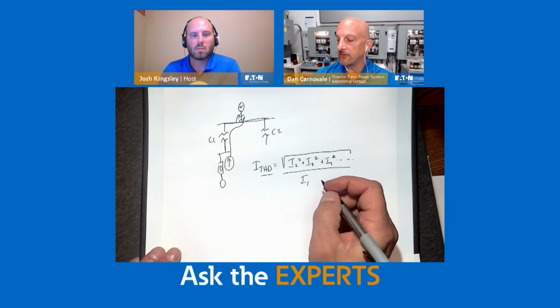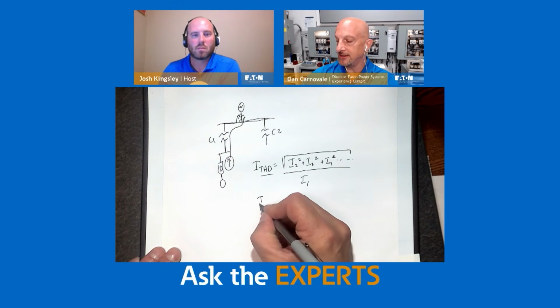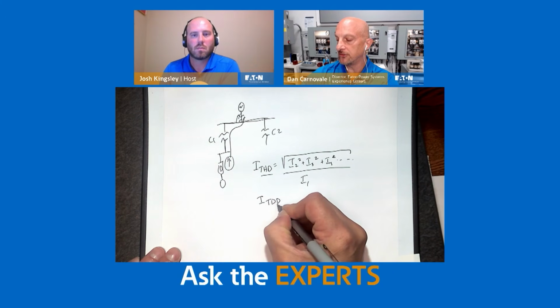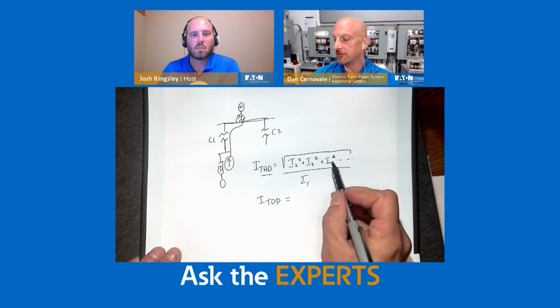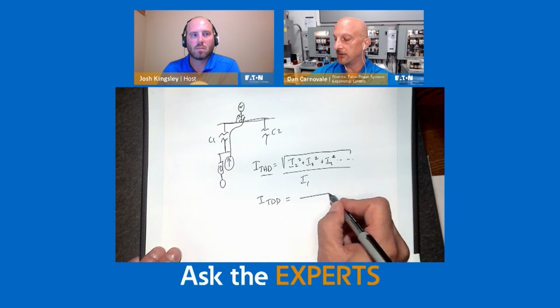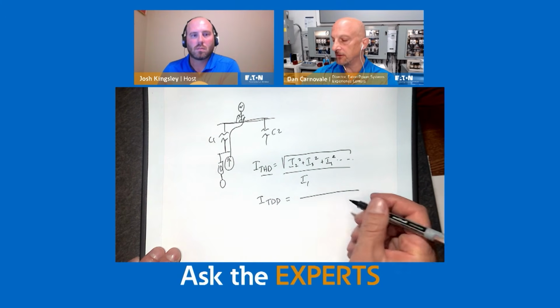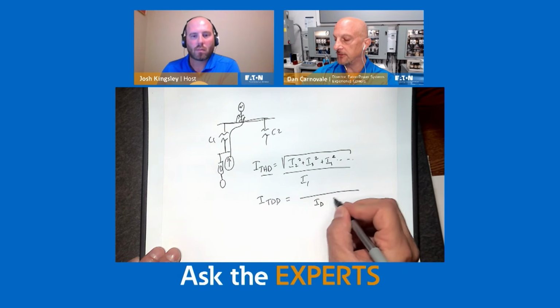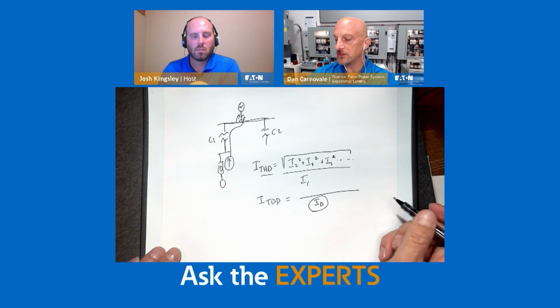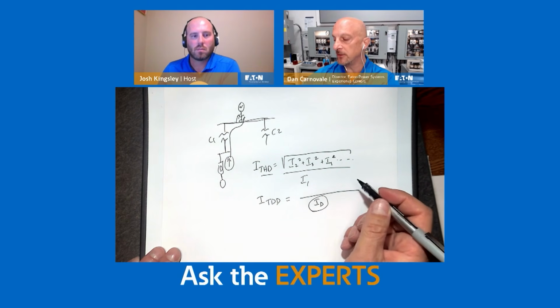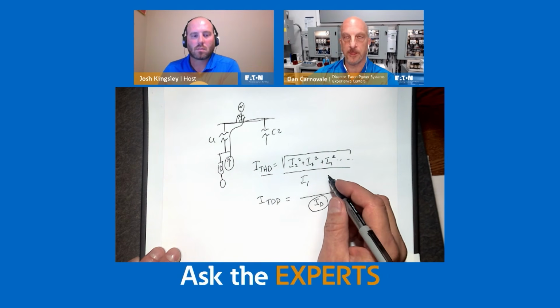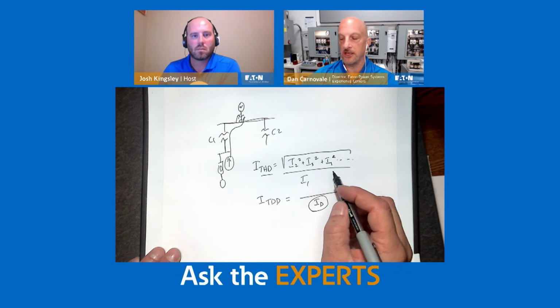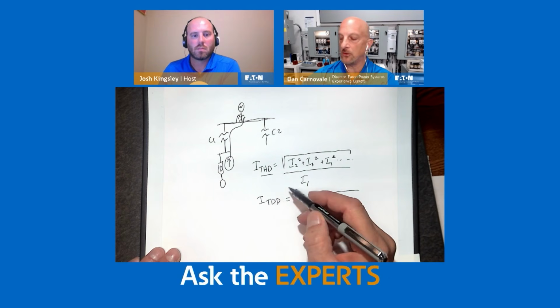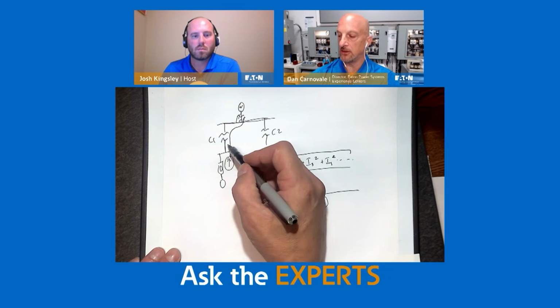With the IEEE 519 standard, they changed that to ITDD, total demand distortion. And what that means is everything on the top is relatively the same, except you're using kind of a worst case scenario demand. And then this is the demand situation when you're at your peak. So you might have really light distortion, or let's say in terms of amps overnight, but the THD could be very high, but your TDD is what's important. So how badly are you screwing up the current on the system according to the size of the system?